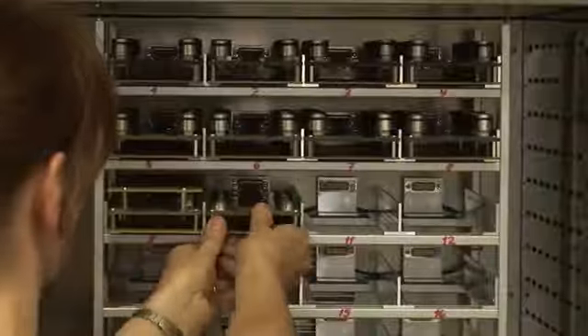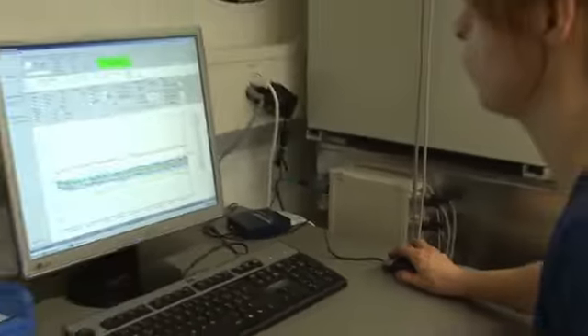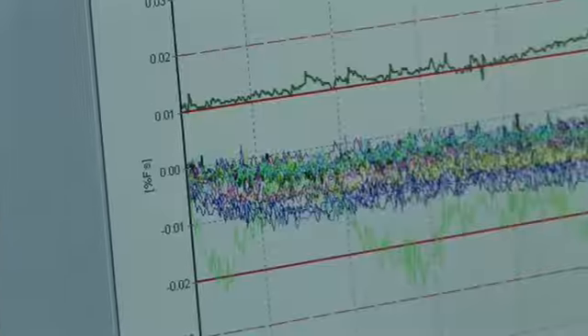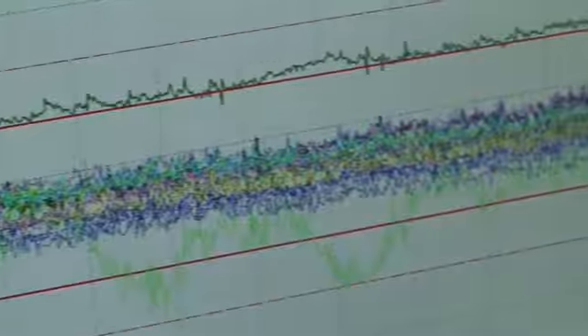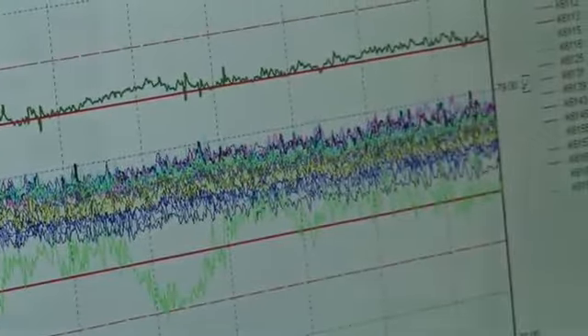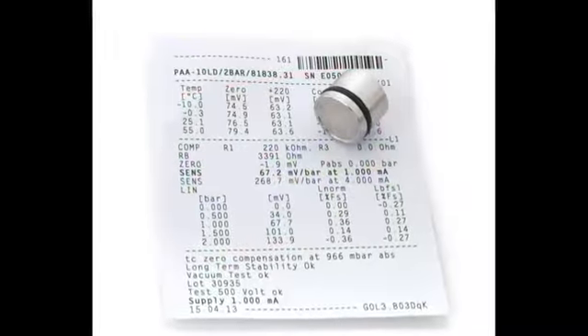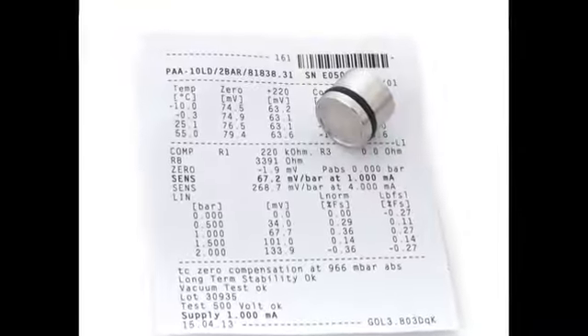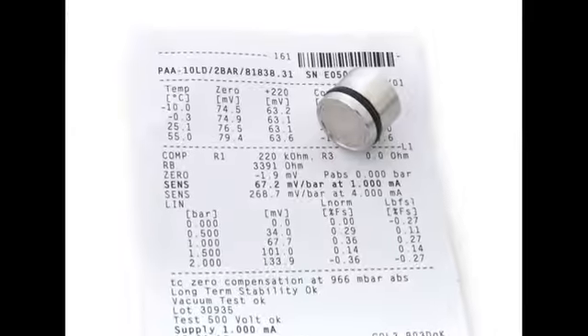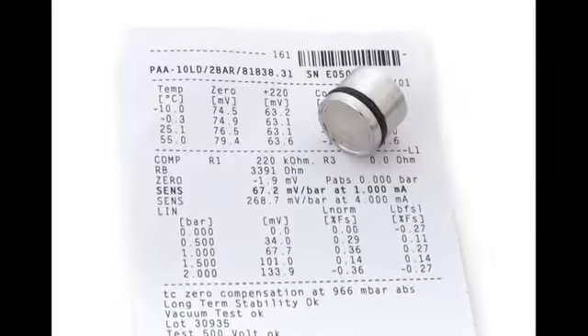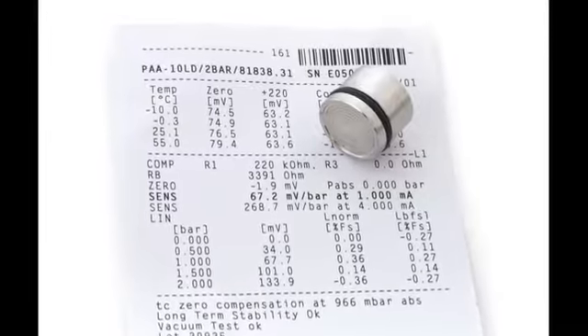The characteristics determined from this process, as well as any additional information regarding the manufacture and compensation, are enclosed with the product in the form of a calibration certificate. More than 1 million insulated pressure measuring cells are delivered and installed every year and carry out their work day by day, hidden discreetly within devices.